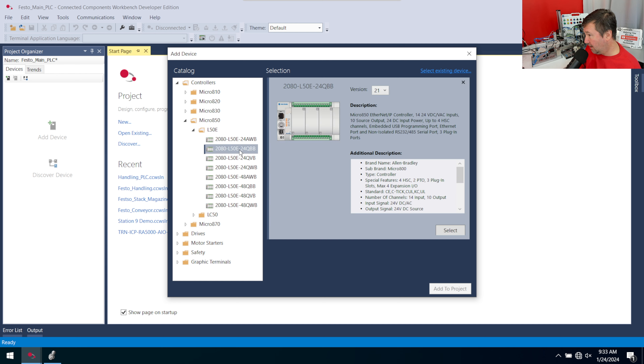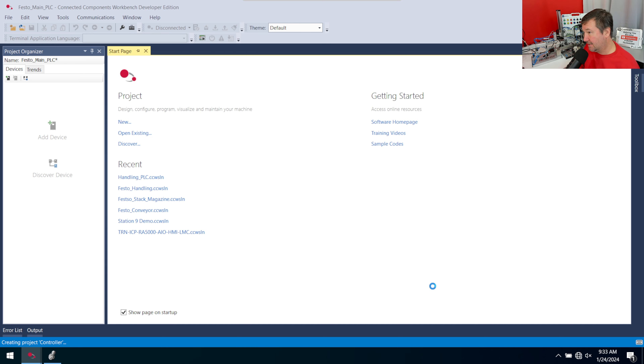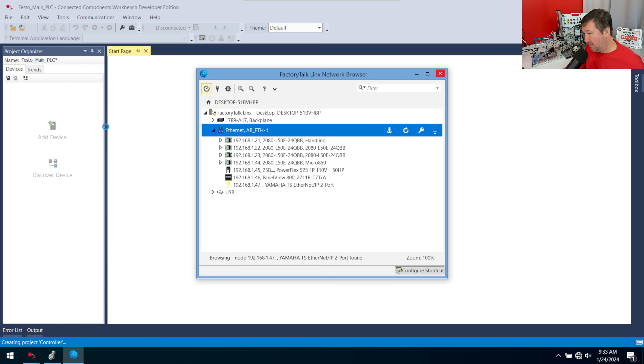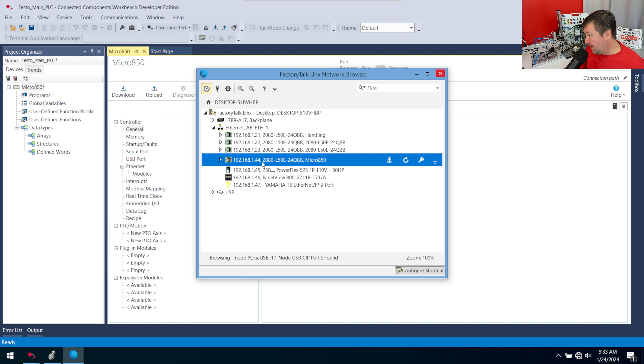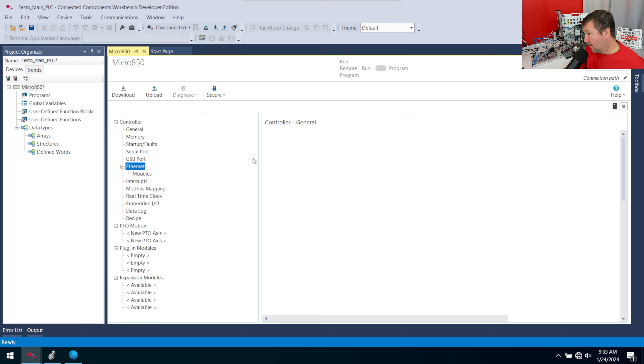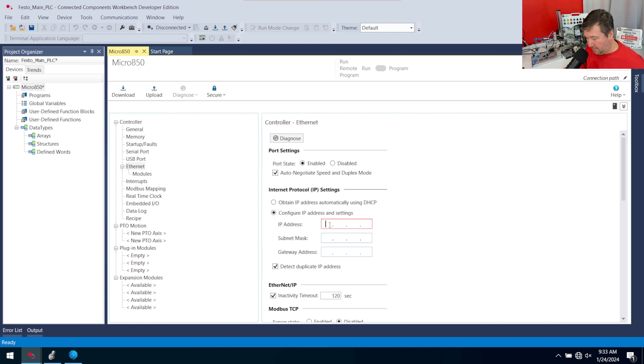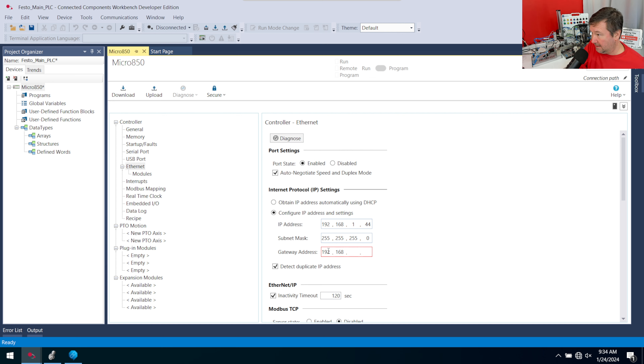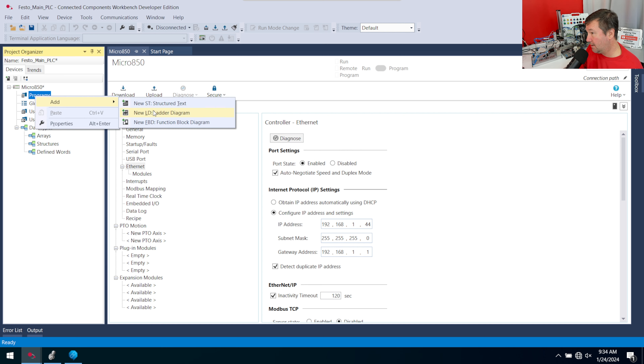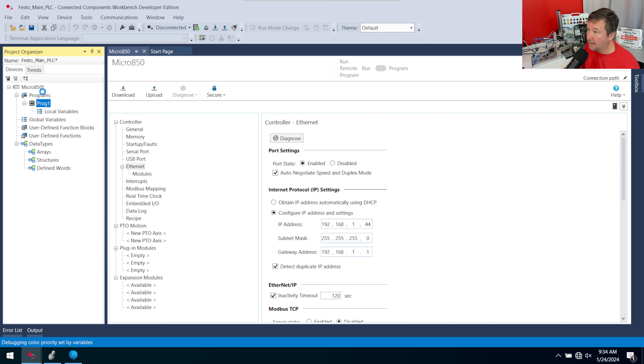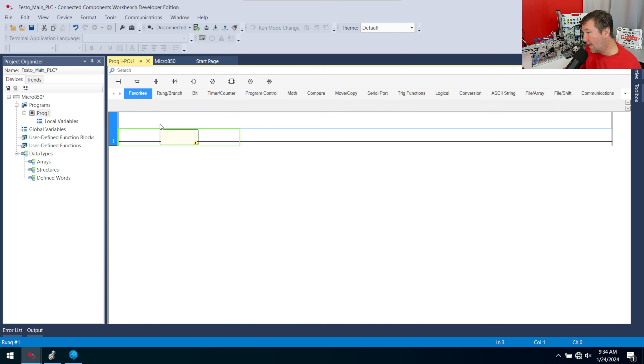Go to controllers — this is also a micro 850 L50E, 2080-L50E-24QBB. Select, add to project. While it loads, let's configure the ethernet settings. This one is assigned as 192.168.1.44. Go to ethernet, select configure address, put in 192.168.1.44 with a subnet of 255.255.255.0. Right-click Programs, add ladder diagram, open prog one, and bring down an instruction block.